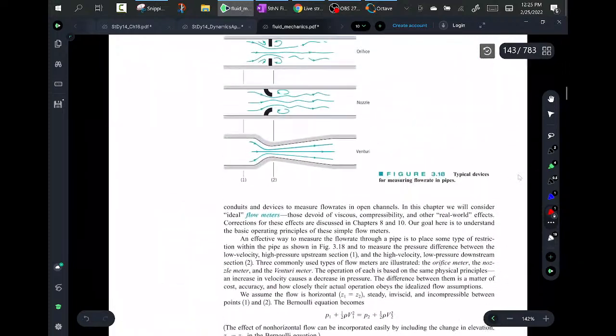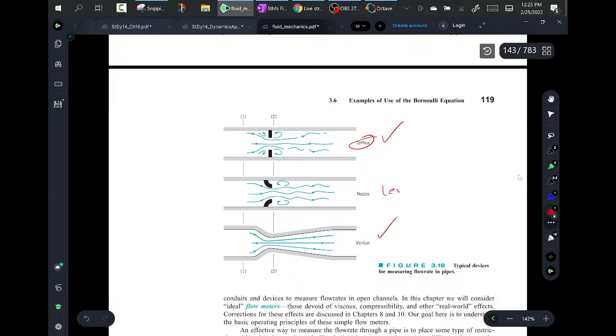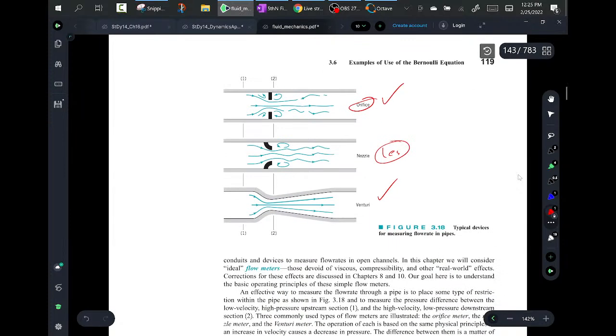Okay, in a flow rate measurement device, they use this concept. In other words, there's orifice meters. This is very, very common. A little bit less common, but it's still out there, is where you're turning the flow. In either case, what you're doing is constricting it, and you're measuring the pressure between here and some spot up here in all of them.